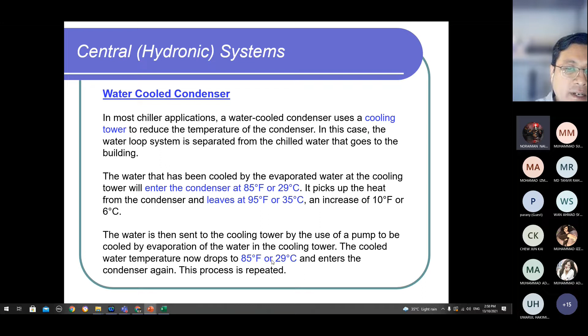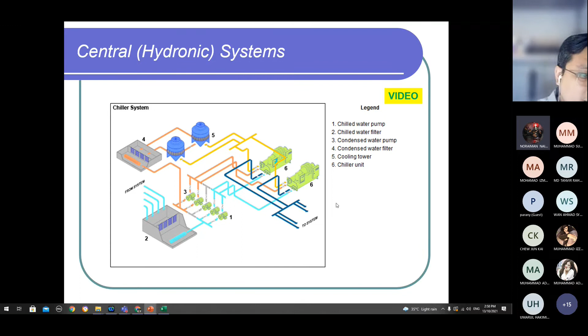It is heated up by the condenser and leaves at 95 degrees Fahrenheit or 35 degrees Celsius, an increase of 10 degrees Fahrenheit or 6 degrees Celsius. Water is then sent to the cooling tower by the use of a pump. Then the cooling water temperature becomes 85 degrees Fahrenheit again and enters the condenser. Then the process is repeated. Okay. This one is the schematic of one cycle in the hydronic system.